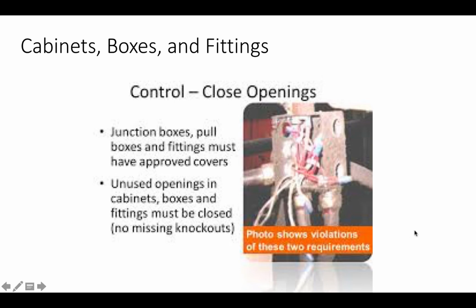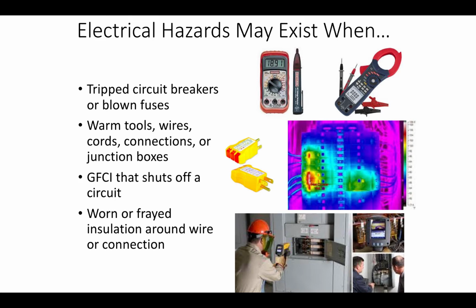This is a photo that shows violations of these two requirements. The knockouts on the side are missing, and there's no cover. And based on the wiring, you cannot get a cover on it. Electrical hazards may exist when there are tripped circuit breakers or blown fuses, if you have warm tools, wires, cords, connections, or junction boxes, a GFCI that shuts off a circuit, or worn or frayed insulation around a wire or connection. If you take a heat sensor, an infrared camera, and take a picture of a breaker panel, you can see hot spots. If there are hot spots, there's a potential electrical hazard.